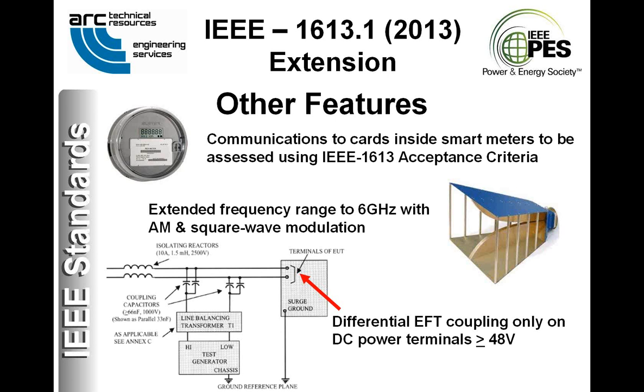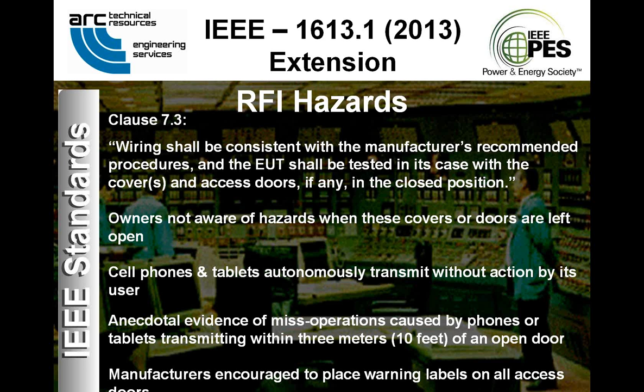We even talked about that incident in 2012, cell phones and tablets that can autonomously transmit without any action by the user. There has been evidence of misoperations, as I mentioned, by cell phones that are transmitting within 3 meters, about 10 feet, of an open door on a networking device. So manufacturers are now encouraged by this clause to place warning labels on all their access doors and covers that alert the user that a misoperation may occur if they're left open, and that the phones or tablets shouldn't be allowed closer than 3 meters from that equipment.